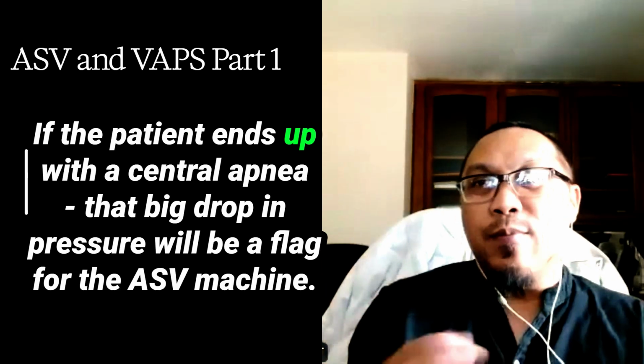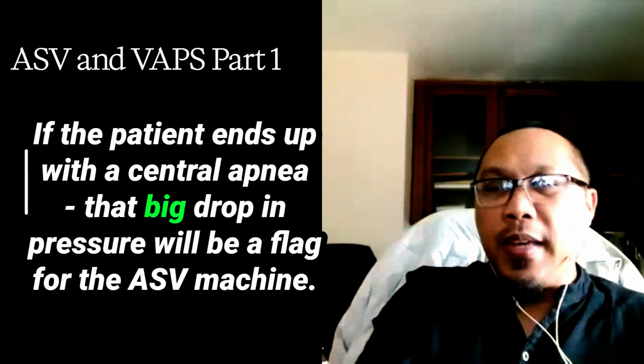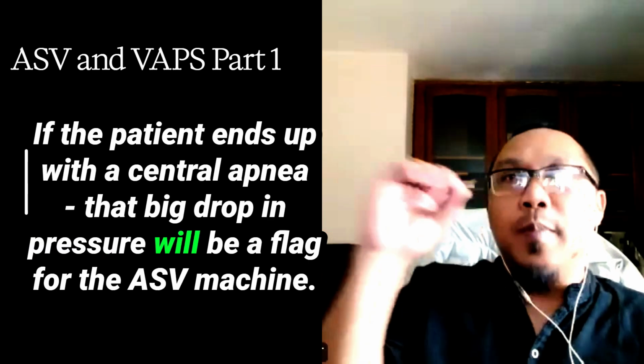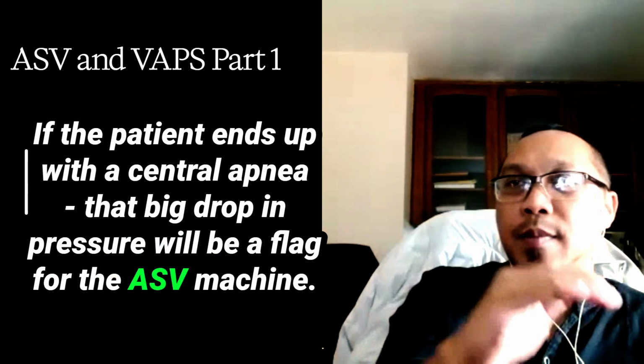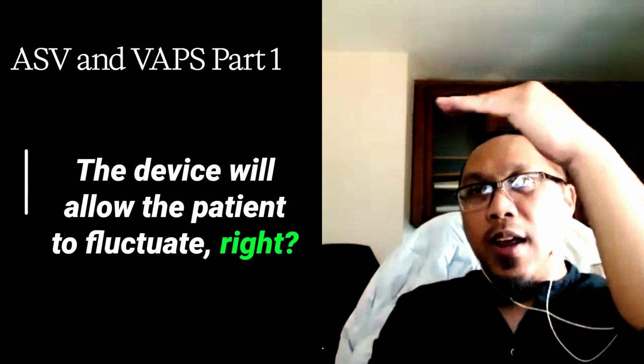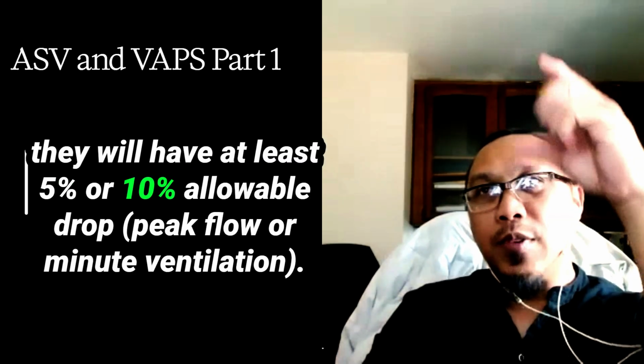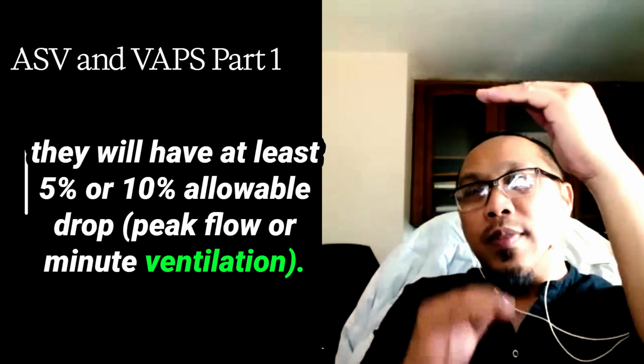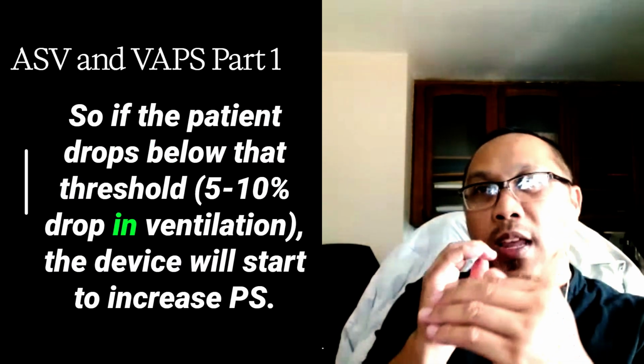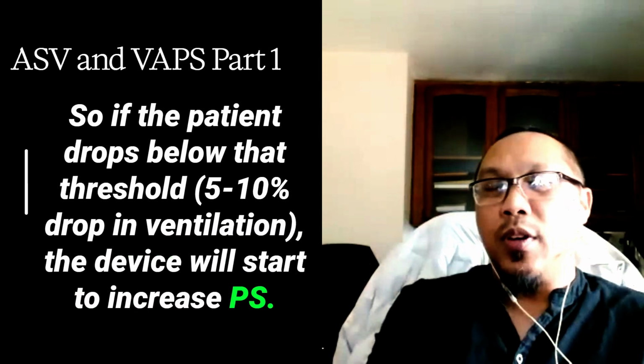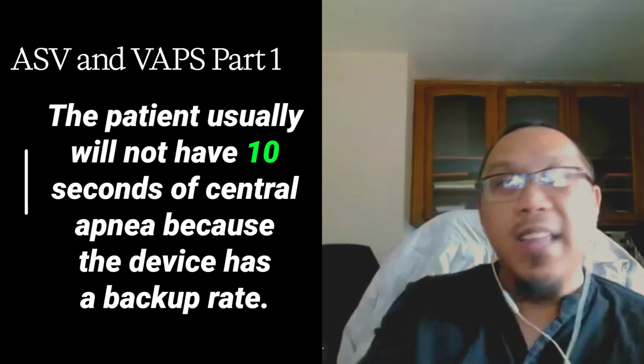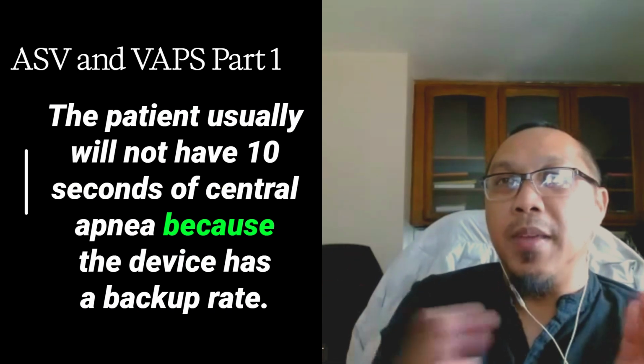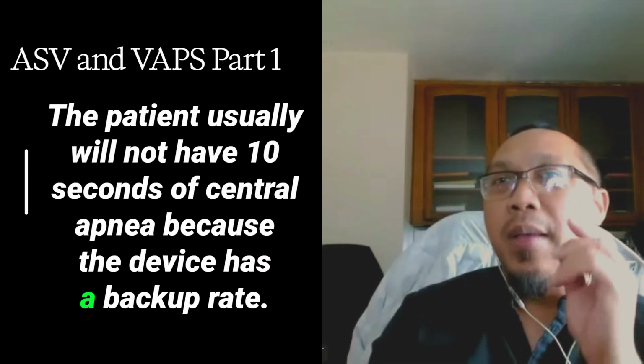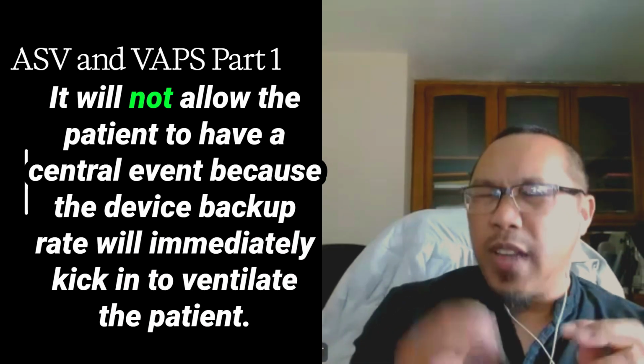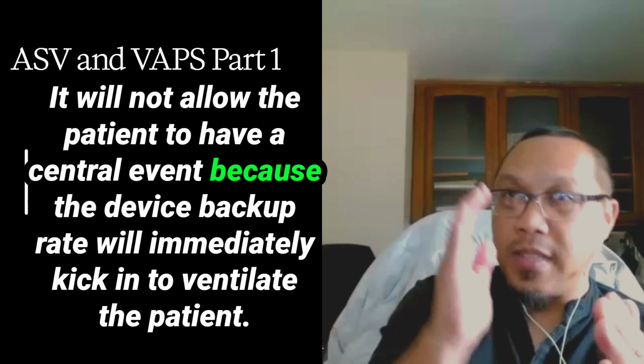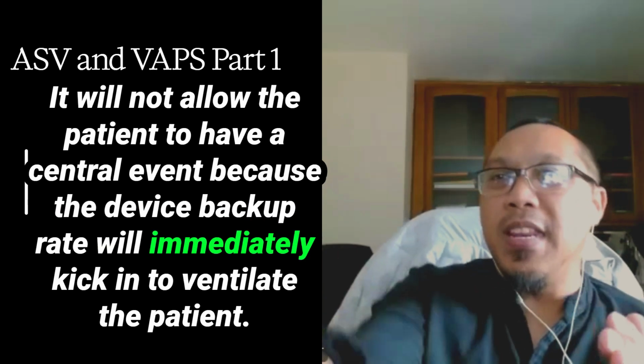If the patient ends up with a central apnea, that big drop in pressure will be a flag for the ASV machine. The device will allow the patient to fluctuate. They will have at least 5 or 10% allowable drop. So if the patient drops below that threshold, the device will start to increase pressure support. The patient usually will not have 10 seconds of central apnea because the device has a backup rate.